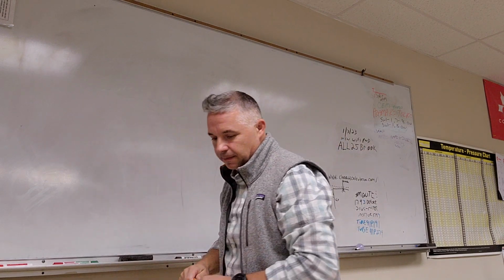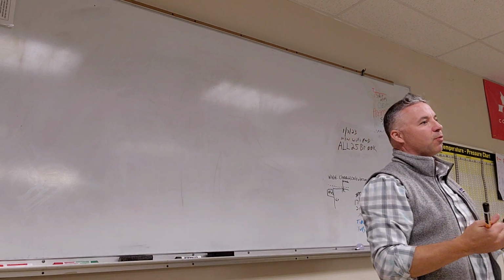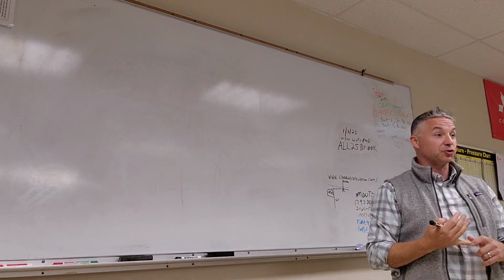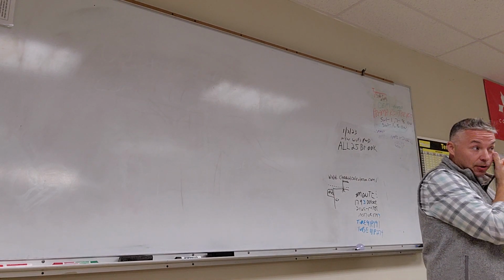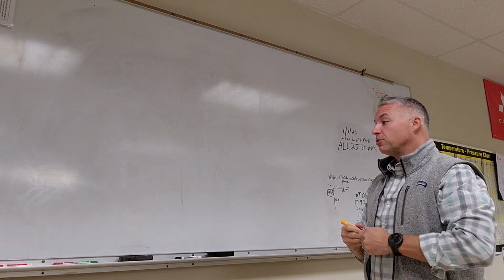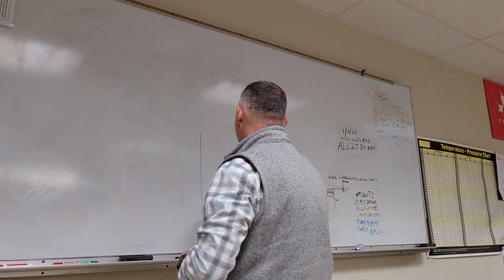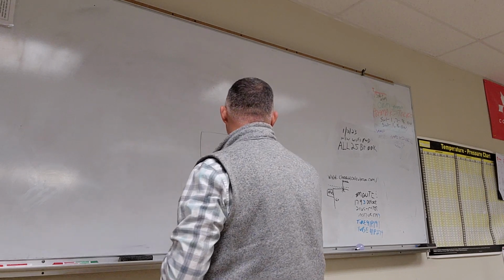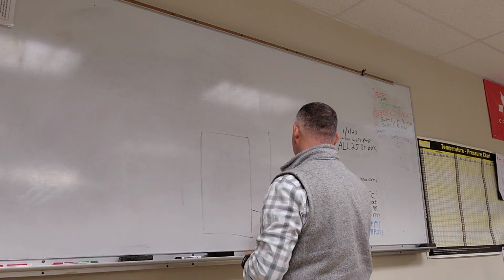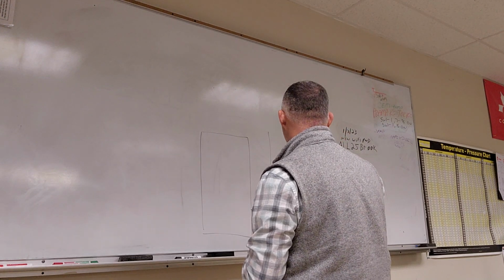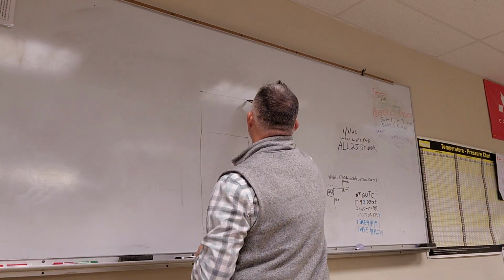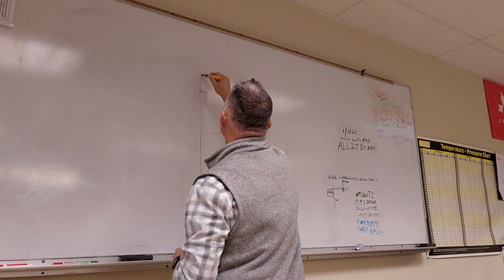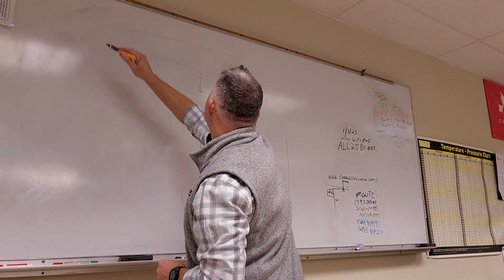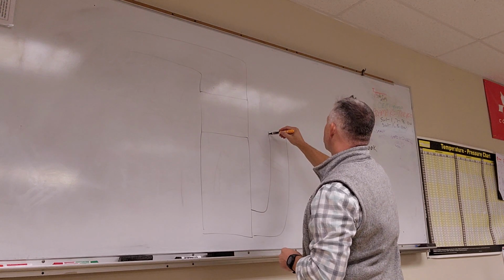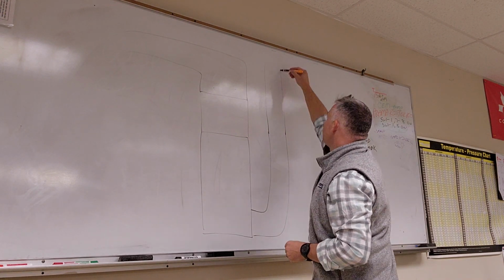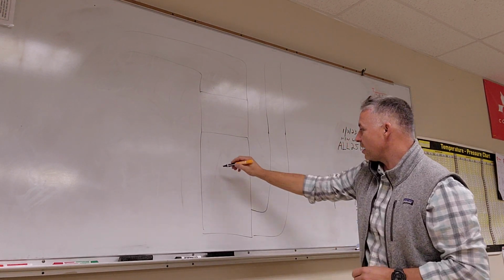So the controls on our steam humidifiers are critical because we want safeties in place to make sure that it's not making too much steam or making steam when it's not supposed to be making steam. So the most important component that we have is our humidistat. And we can call that a high limit humidistat. And I'm going to draw a very basic design and installation for you guys, okay? So you have somewhat of a visual. And here's some ductwork. This is some return ductwork, okay? It's pretty beautiful. I'll agree with that. This is an air handler.